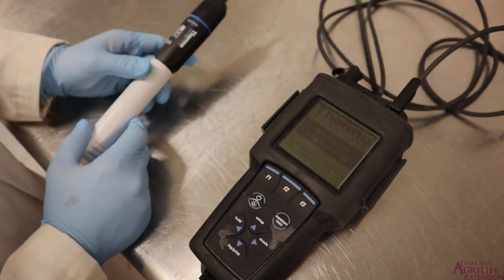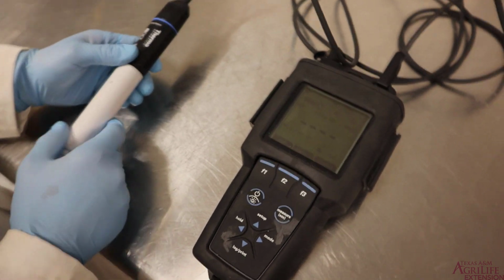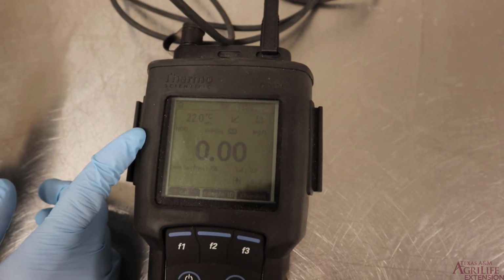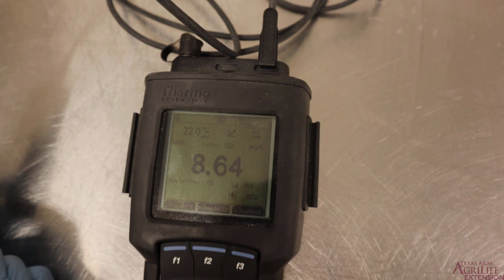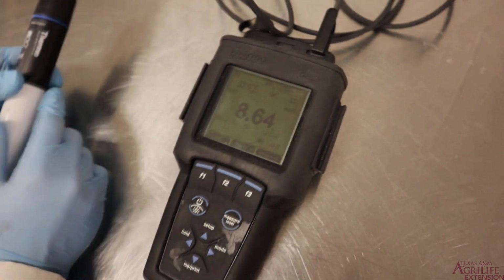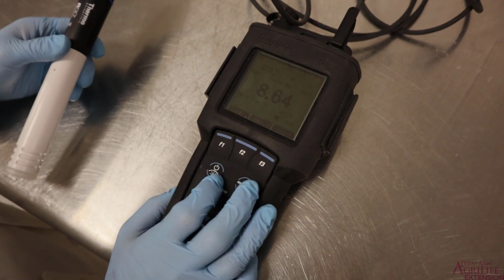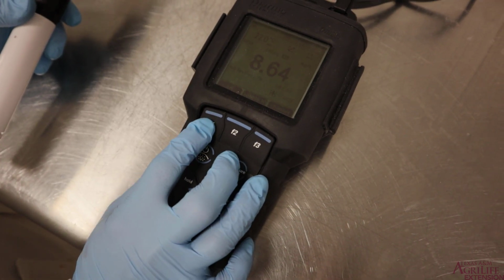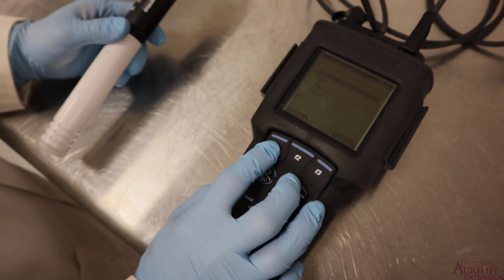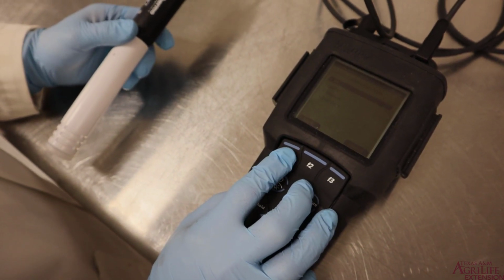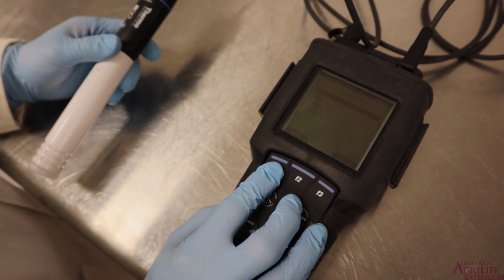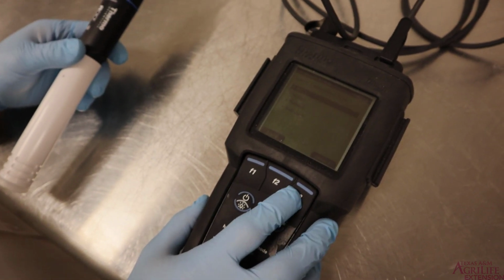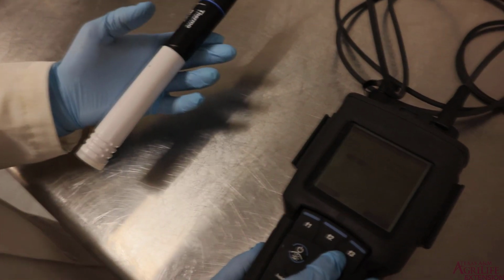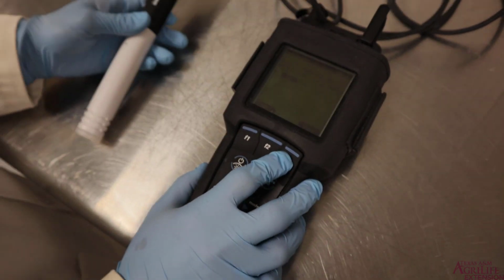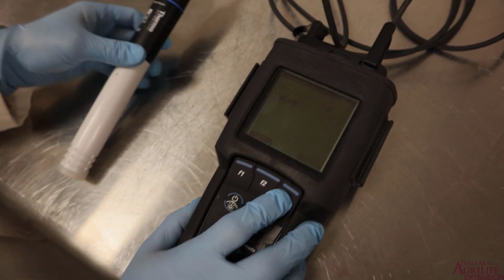Once it turns on, we'll make sure it's on the RDO set, which it currently is right now, and we'll run a calibration on it since it'll be our first time using it today. So to do that, we'll hit F1, the calibrate function, and then it'll give you a list of options: air, water, manual, set 0. We'll go ahead and do an air calibration. We'll keep it in our plastic casing while we do that with our sponge, and we will hit start.